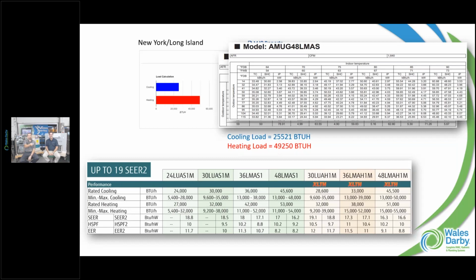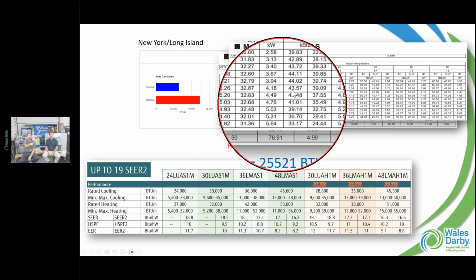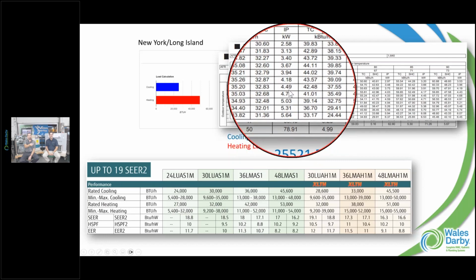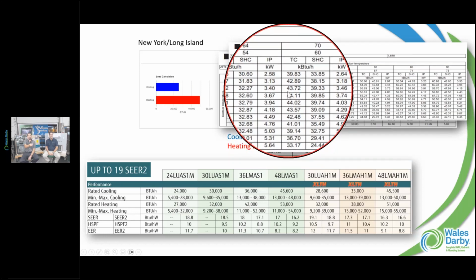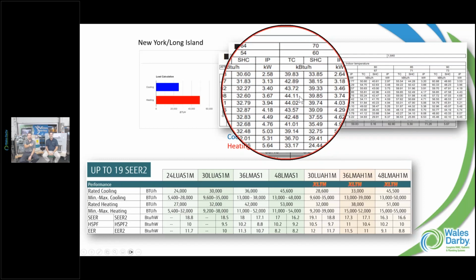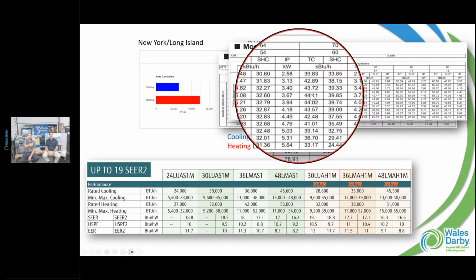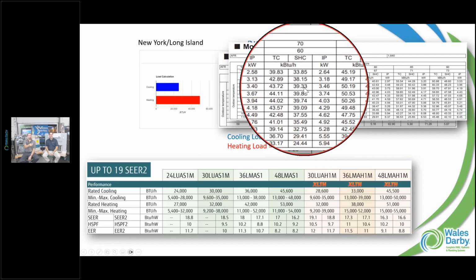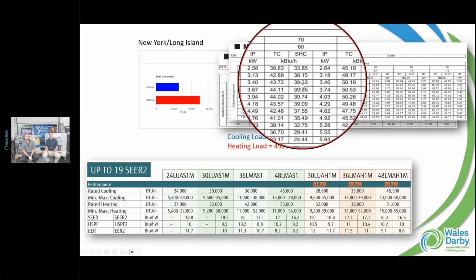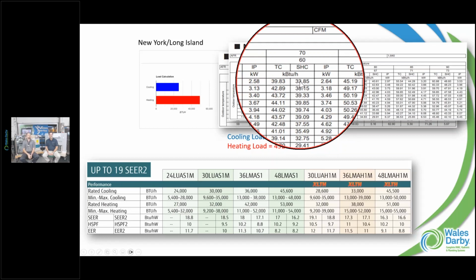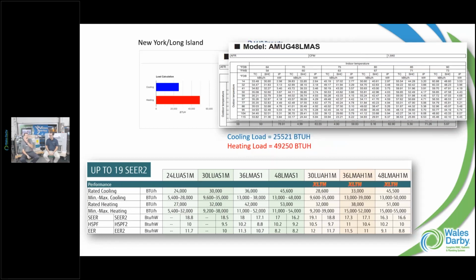TC is total capacity. You have a couple of extra columns, like kW, which is your input power. If we look on that row, our 86 is how far down? Four from the bottom. Oh yeah, I see it. So we're getting about 41,000 BTUs total capacity. I apologize for the Zoom thing, it's a little finicky for us. It actually widens the circle. So that's a lot of BTUs, 41,000, when we've got a total load of 25,000 on an 86-degree day.